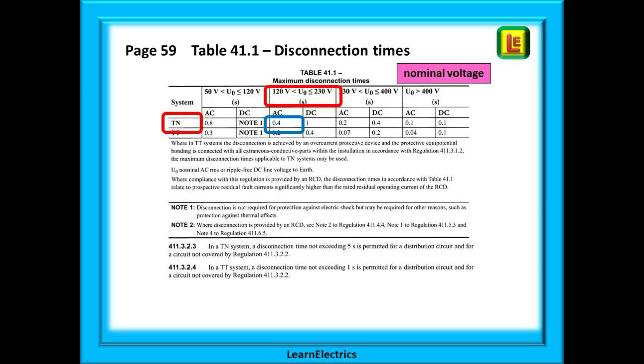For the kitchen at 230 volts nominal we will use the second block of data. The symbols at the top mean the nominal voltage is over 120 volts and up to and including 230 volts. Then on the left we can choose the earthing system. Using TN — shorthand for TNCS or TNS systems — where the column and row cross we have 0.4 seconds, and this is our maximum disconnection time.